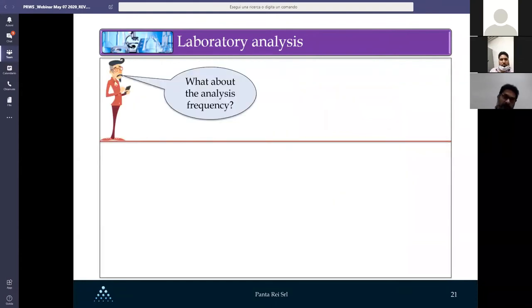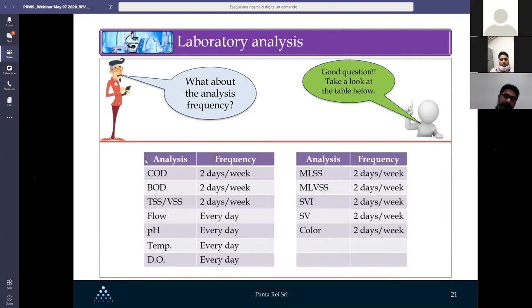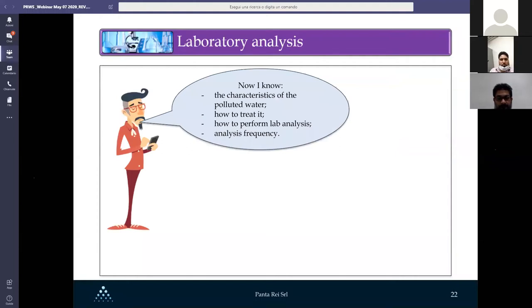Regarding analysis frequency: COD, BOD, solids, MLSS, VSS, and SVI should be measured two days per week. Flow, pH, and temperature should be monitored every day to track ETP performance. John now knows the characteristics of polluted water, how to treat it, how to perform laboratory analysis, and the analysis frequency.